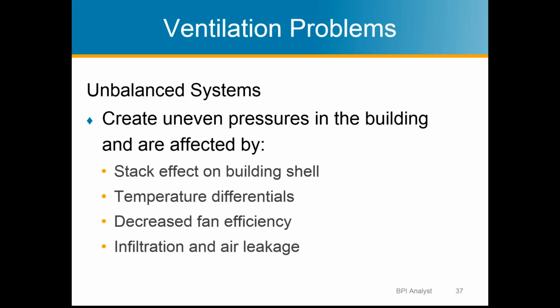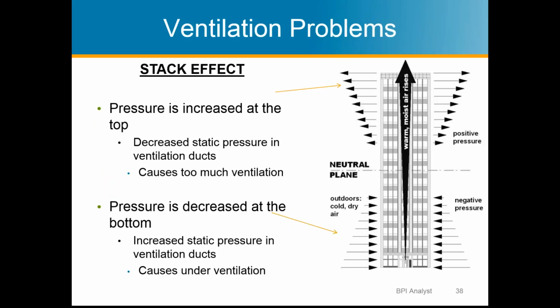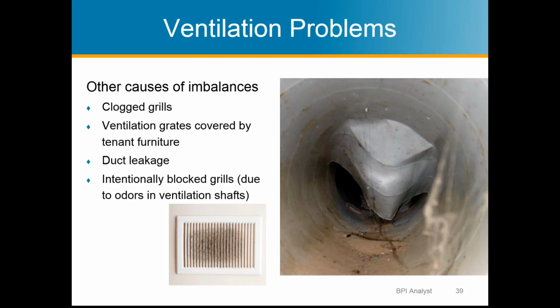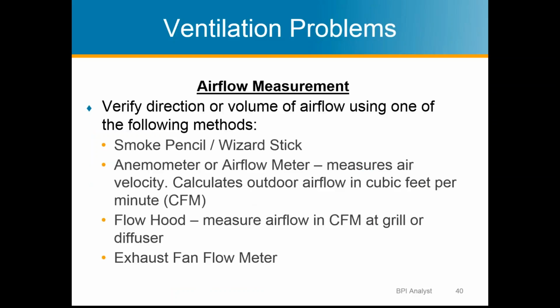Unbalanced systems are also often affected by temperature differentials, by the stack effect. Oftentimes you can decrease fan efficiency because you've got a large negative pressure in the house. And then just the infiltration. You're bringing in unconditioned air into the house in various places. So stack effect, same thing. Most homes are probably going to be no more than 2 stories, so it's not going to be a large pressure differential created by the stack effect that will have an adverse effect on your ventilation, but it will affect it in some amount. And then also just clogged systems, of course, clogged grills and holes in the ductwork.